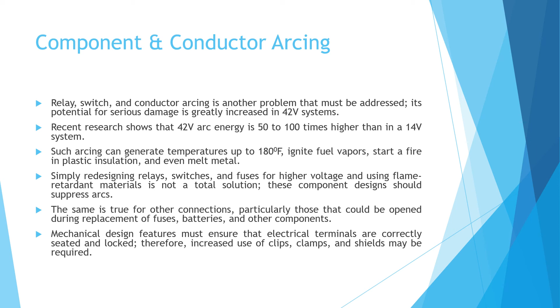The component's design should suppress the arcs. The same is true for other connections, particularly those that could be opened during the replacement of fuses, batteries and other components. The mechanical design features must ensure that the electrical terminals are correctly seated and locked. Therefore, increased use of clips, clamps and shields may be required.